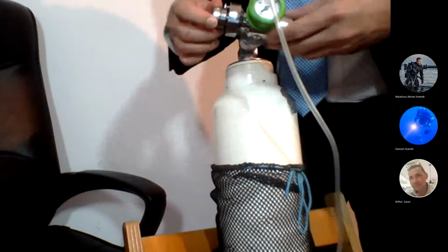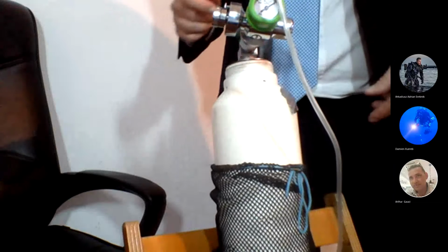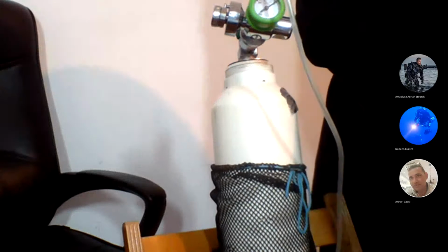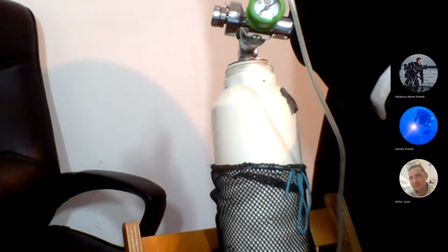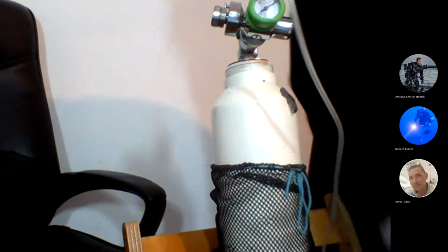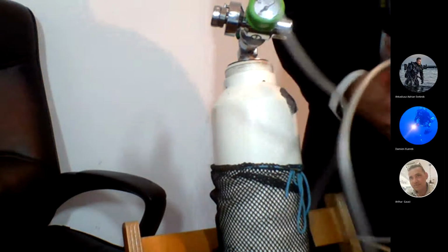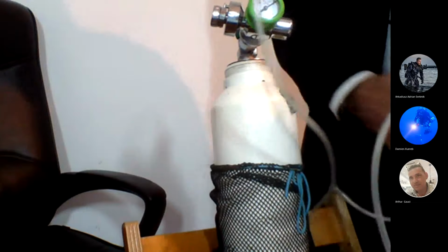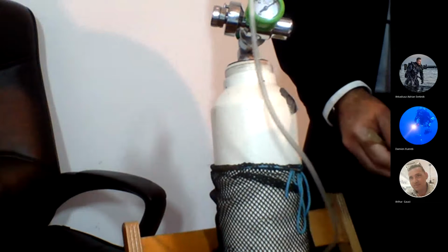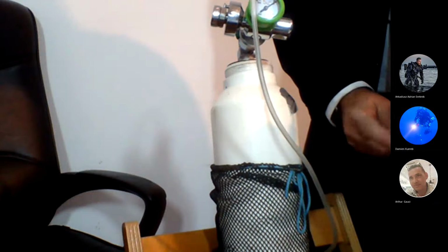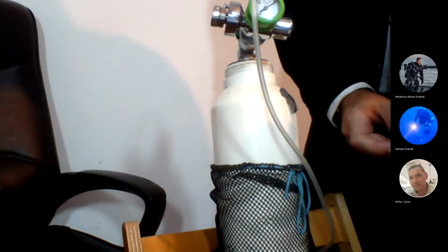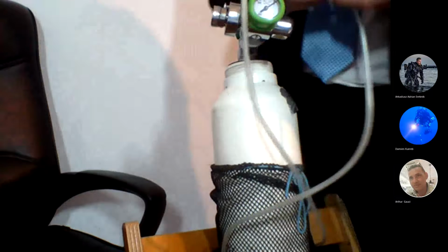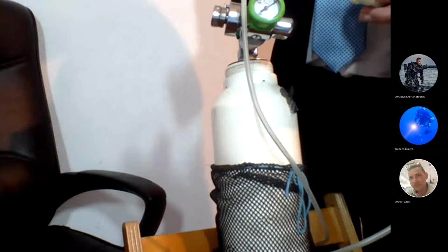That's because the sensor is good, and I really believe the quality of these sensors is special. But if you under-calibrate, say it's 21% and you calibrate it to 20, when you put it on 98 or 99% oxygen, will it not show 100% as well? Correct, absolutely, it will show 90%, something low.